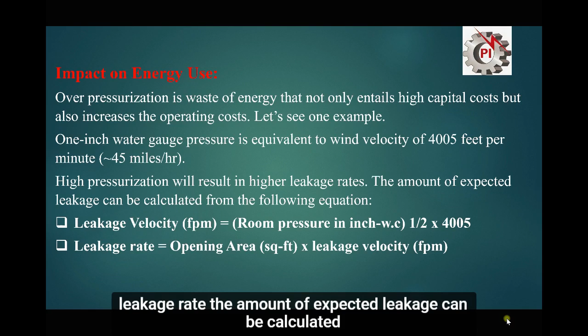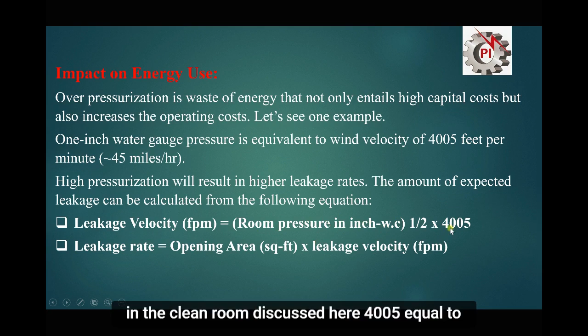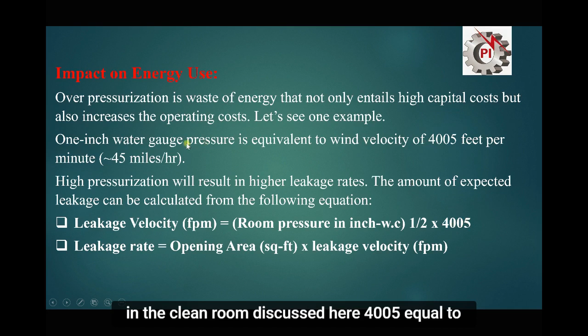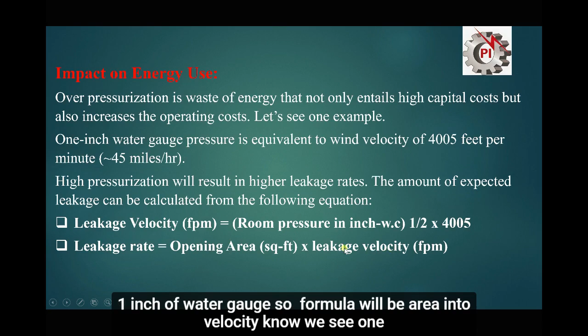From this equation we can find the velocity of leakage. It uses the room pressure in inches of water gauge, meaning how much positive pressure we are creating in the clean room, multiplied by the wind velocity as we discussed here, 4005 equal to 1 inch of water gauge. So the leakage rate formula will be area times velocity. Now we will see one example.